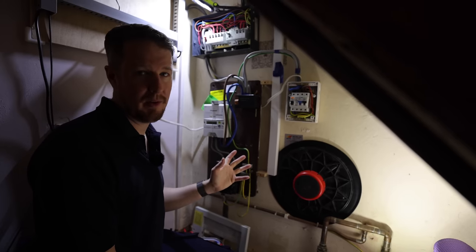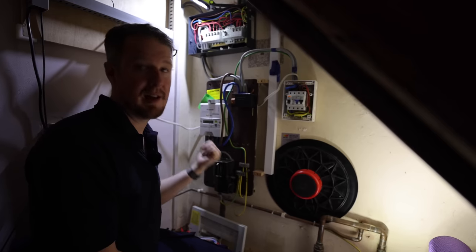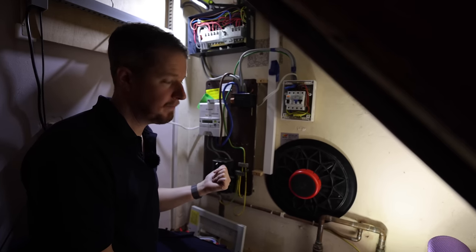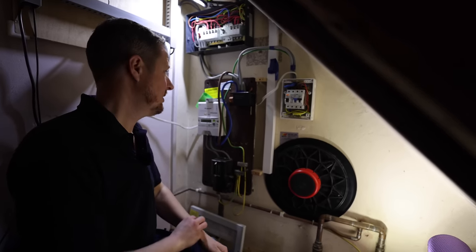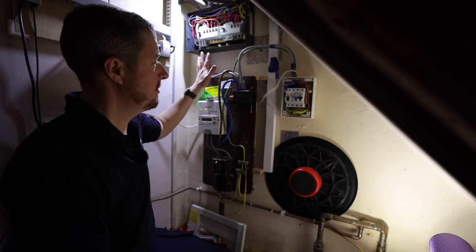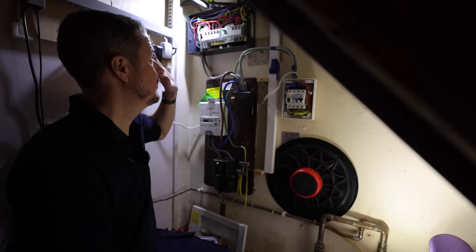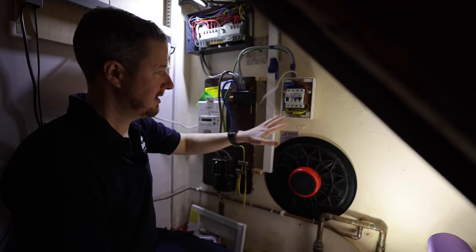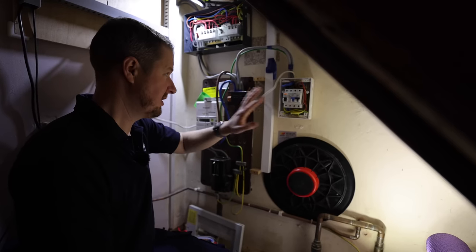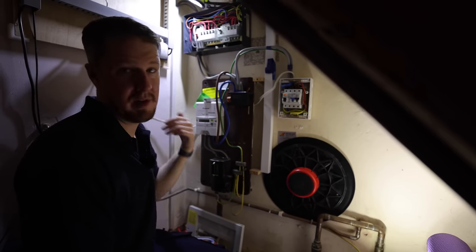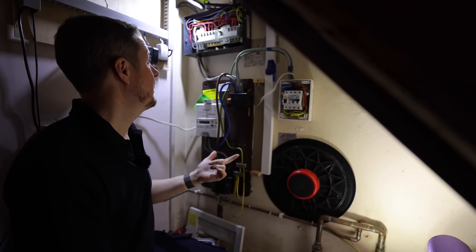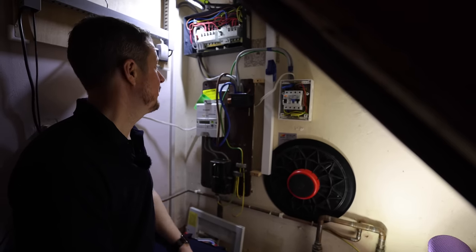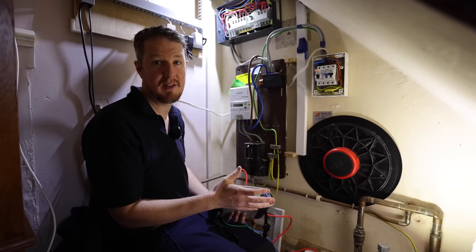To give you a bit of background on this job, the customer initially contacted us because they wanted an electric vehicle charging point installed. That is the reason why we're doing this EICR first, because the existing consumer unit is too old to fit a new circuit. This consumer unit just looks like a bit of a bodge, so I said to the customer we'll do an EICR first, we'll put a new consumer unit in because it's kind of time for an upgrade really anyway, and then we'll install the EV charging point.